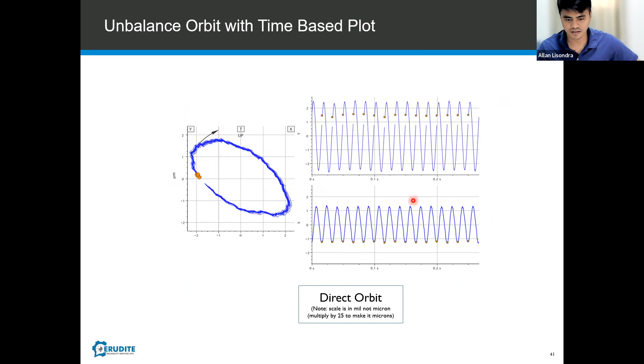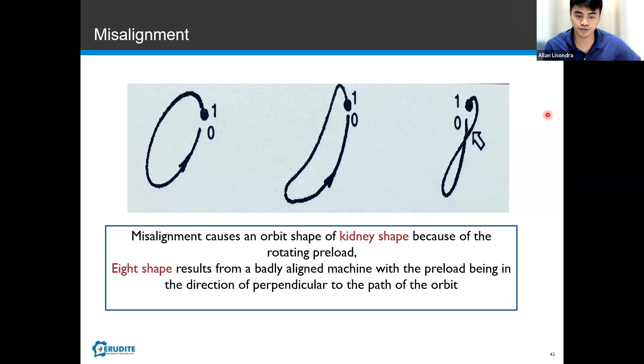Next, we have misalignment. It is also like an orbit, but a little shifted and squeezed, because there is preload — when you're preloaded, it gets pinched. So misalignment causes an orbit shape like a kidney shape. As misalignment worsens, it becomes more of a kidney shape, and after that, an eight shape. The H shape results from a badly aligned machine with preloaded bearing in the direction perpendicular to the path of the orbit — this is the example of misalignment when it's badly misaligned. But of course you have to take note of the amplitude too, because if it's very low but showing some misalignment, it may still be within the acceptable limit, since in alignment we also have these limits. But as you work with your system, you become more familiar with what is happening, like having a trend so you know if it's increasing or not.